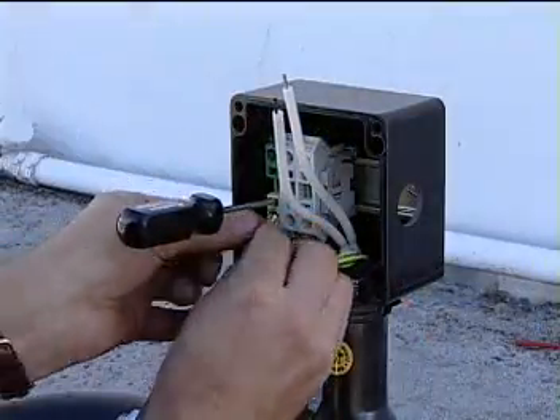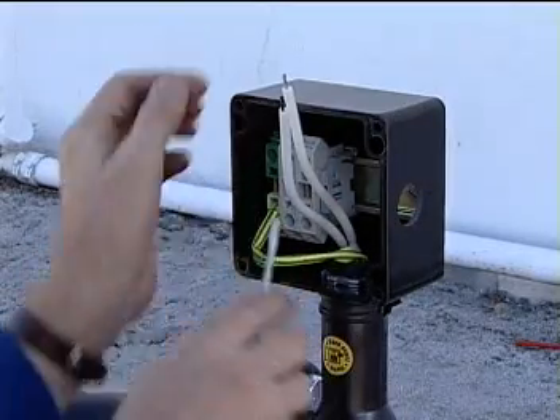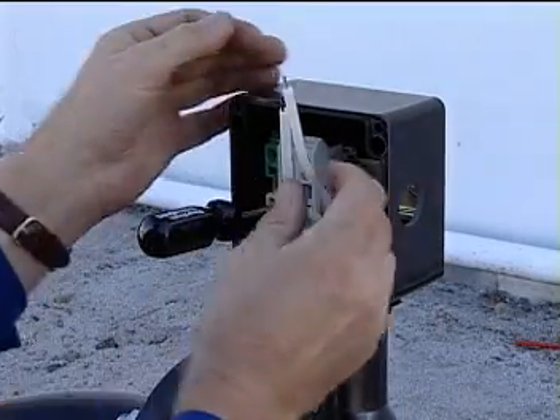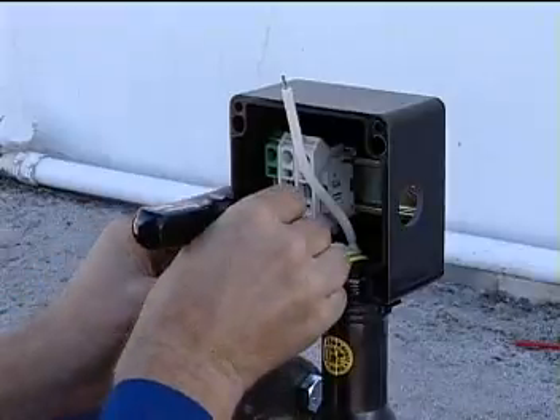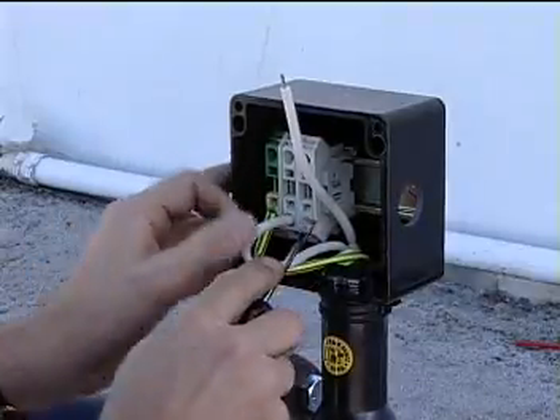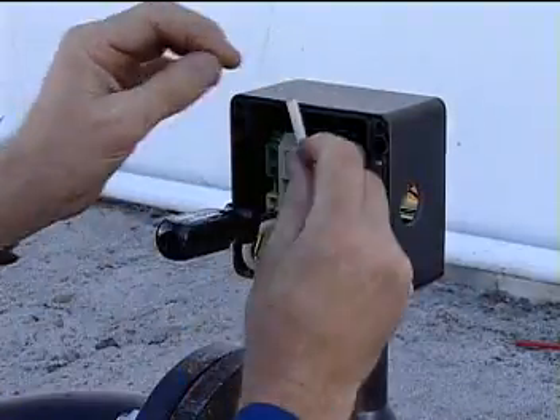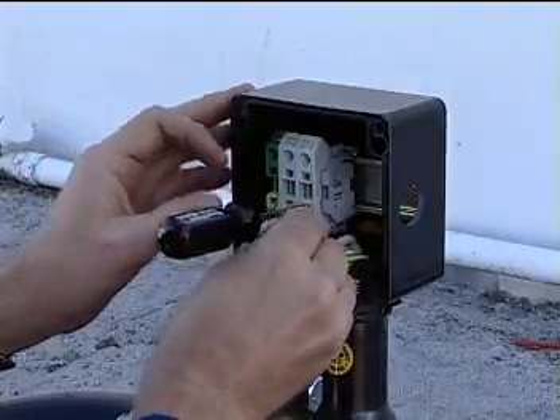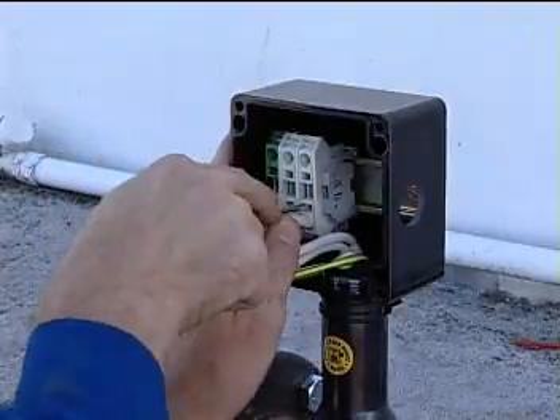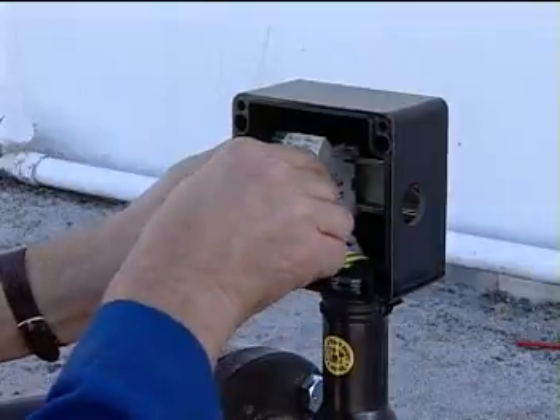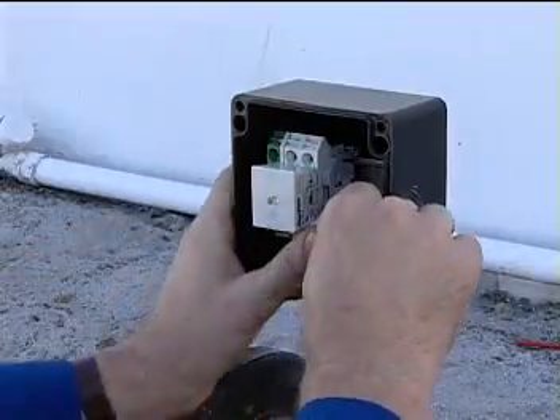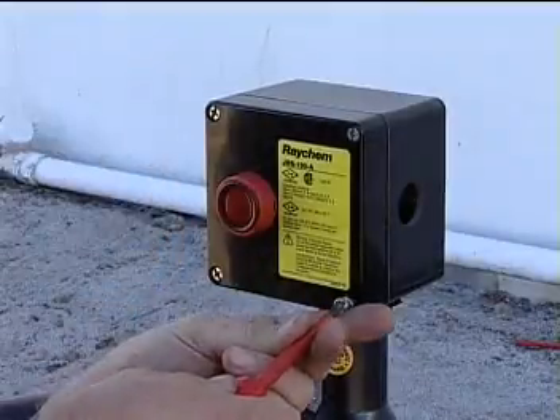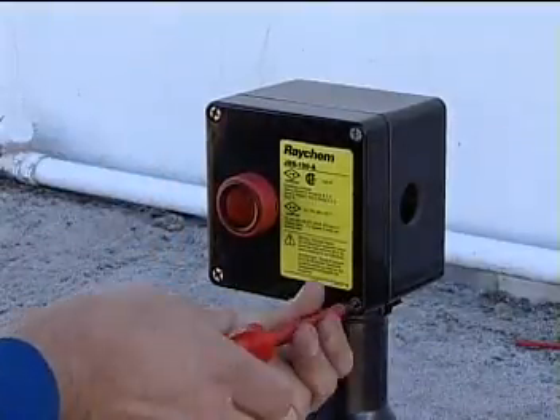Next, to connect the bus wires and braid to the terminal block firmly, insert a flat blade screwdriver into the square hole to open the spring. The screwdriver will lock into place, allowing you to remove your hand and insert the wire into the round hole. Remove the screwdriver to clamp the wire. If you have a connection kit with a signal light, simply plug it into the terminal blocks before installing the lid. Finally, stow the wires in the enclosure and fasten the lid in place.